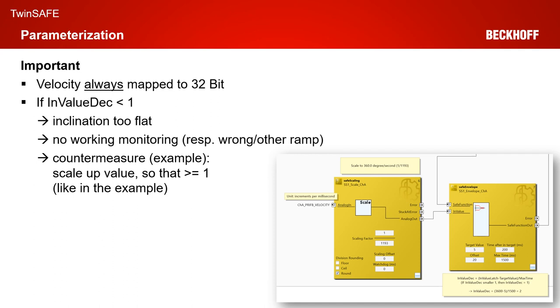Respectively, the wrong ramp is monitored. As a countermeasure, as shown in our tutorial today, you can scale up the value so that the decrement value is greater or equal to one. In our example, we initially wanted to scale to 360 degrees per second but the decrement resulted in a value less than one. So we scaled up to 3600 degrees per second, which results in a decrement value of two, giving us the correct ramp function for our application.